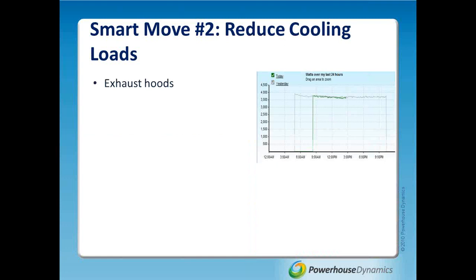So for example, on the exhaust hoods I mentioned, this is a chart that shows somebody starting their exhaust hood later one day than they did the other day. It was, I believe, at 5:30 one morning and at 8:30 the next morning. That 3 hours of exhausting potentially cooled or pre-cooled air is expensive. Ventilation can represent somewhere between 20 and 40% of your entire cooling load, because it is pulling so many CFM through the roof every minute. So making some kind of adjustment to how you're using equipment, of course within reason, is going to make an impact on your cooling bill.